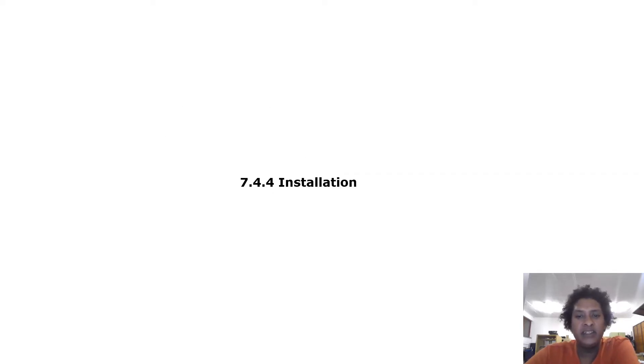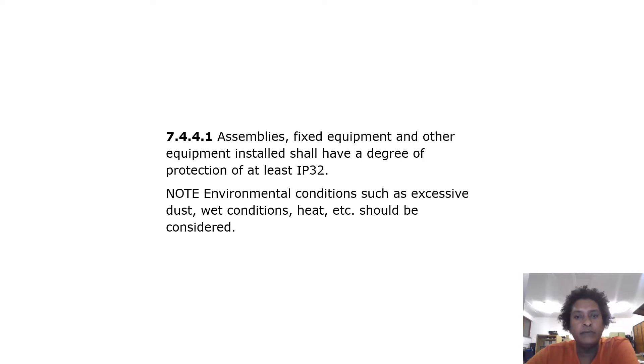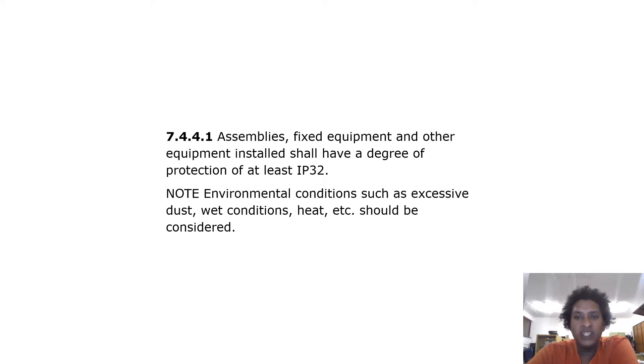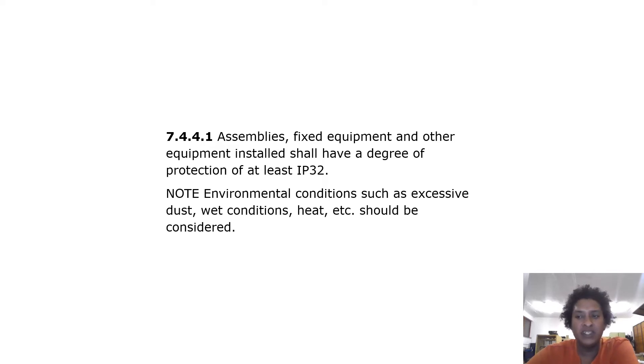Installation. Assemblies, fixed equipment and other equipment installed shall have a degree of protection of at least IP32. Note: environmental conditions such as excessive dust, wet conditions, heat, etc. should be considered.